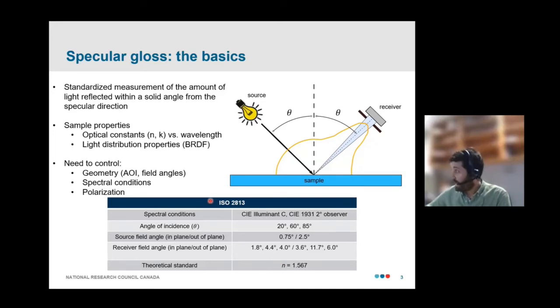And that's exactly what standards like ISO 2813 prescribe. So here I'm showing a table of the various spectral and geometric conditions that are expected for that standard. And of course, as we've heard, the standard is defined such that this theoretical or fictitious black glass of refractive index 1.567 defines 100 gloss units at each angle of incidence.